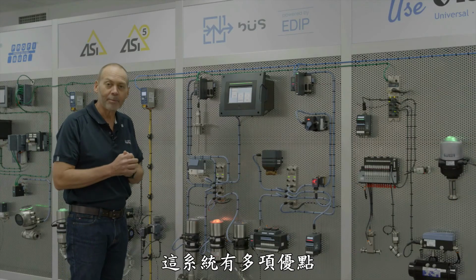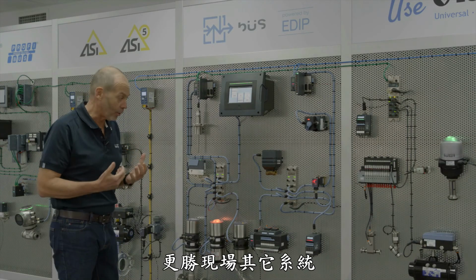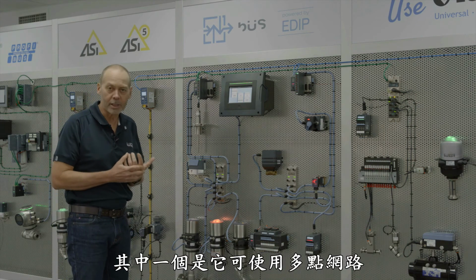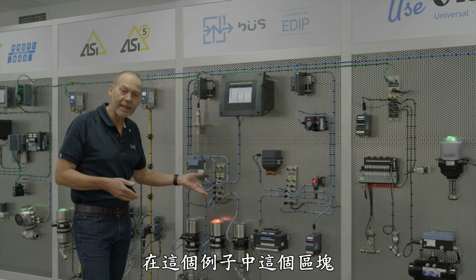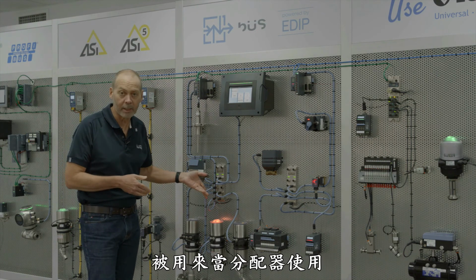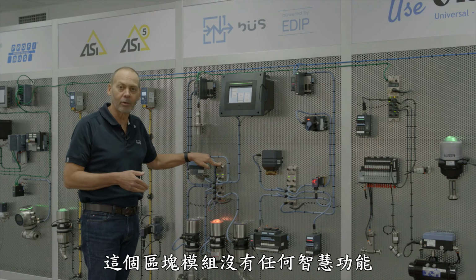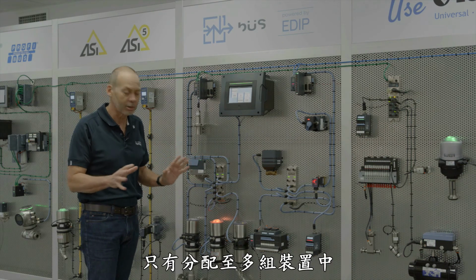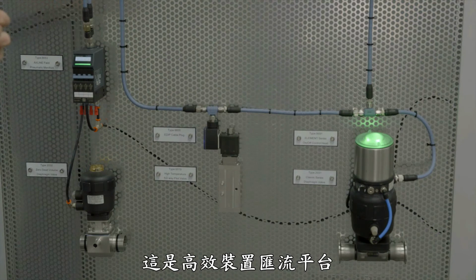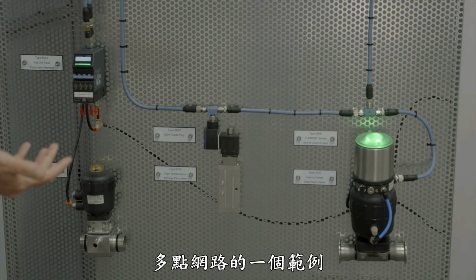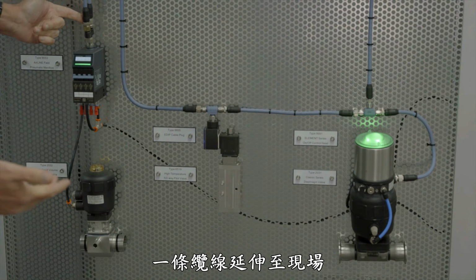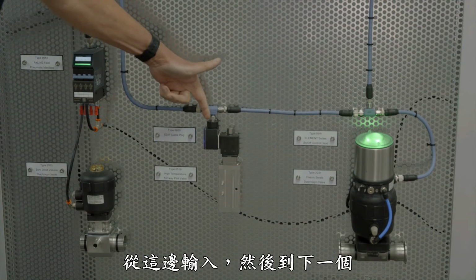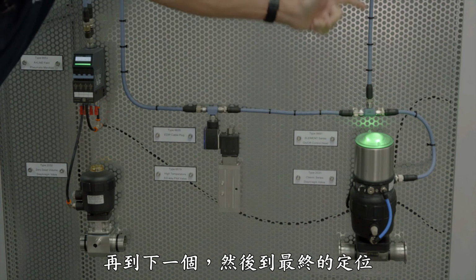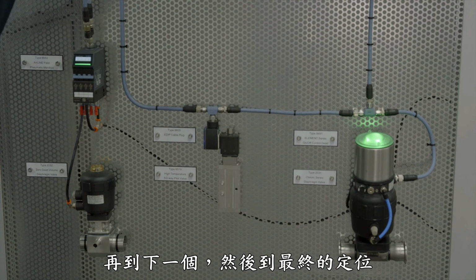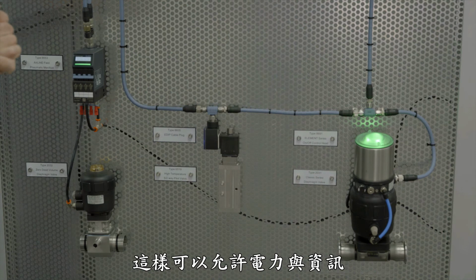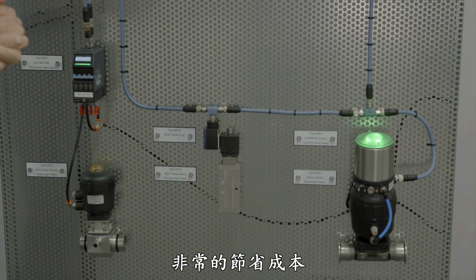The network has a number of advantages over other networks in the field. One of them is the fact we can multi-drop this network. Now in the example here, you'll see these blocks where we're using them as a distributor block. There's nothing smart in this block at all. All we're doing is we're distributing to multiple clustered devices. And this is an example of the multi-drop version of EDIP, where one cable travels to the field, we come in, we go into the next one, to the next one, and of course to an end position. This gives you the ability to take power and data down a straight line in a very, very cost-effective way.